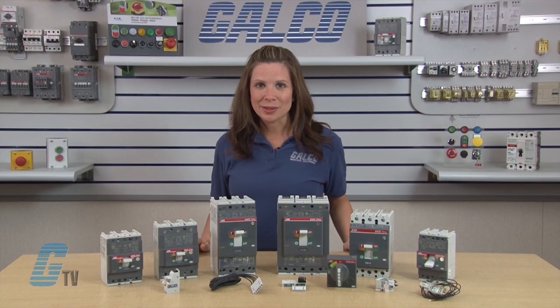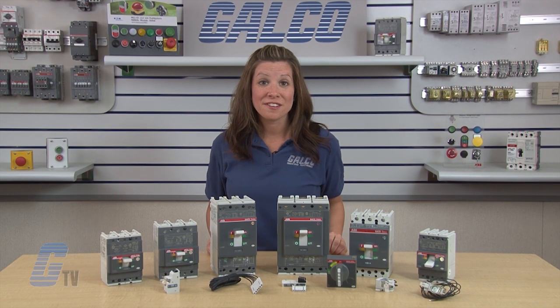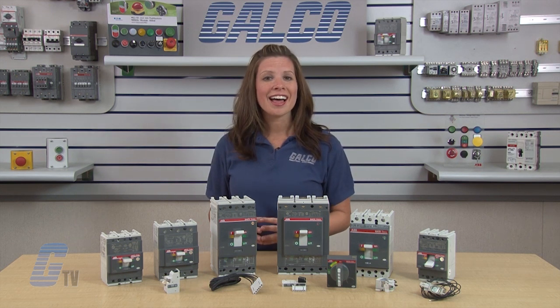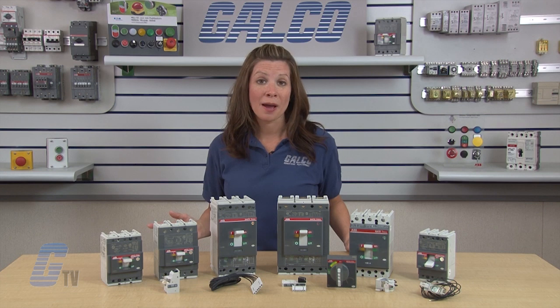The Tmax Series has interrupting ratings at 480 volts AC up to 150 kilo amps interrupting capacity. The double insulation construction characteristic allows for the UL listed field installation of internal accessories without exposure to the power poles.